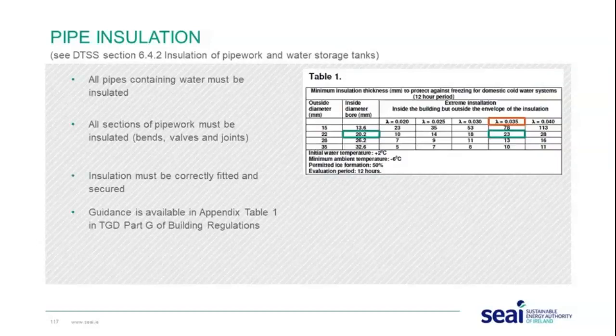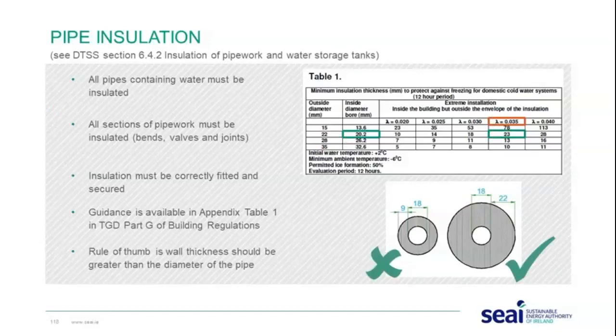As a practical example: for a 20.2 millimetre diameter pipe with pipe insulation conductivity of 0.035, you would need 23 millimetres of insulation. A useful rule of thumb is that the wall thickness of the pipe insulation should be greater than the diameter of the pipe. For example, with an 18 millimetre pipe, 9 millimetre insulation is insufficient — you should use 22 millimetre insulation. The key message is to use thicker insulation where the wall thickness is greater than the pipe diameter.